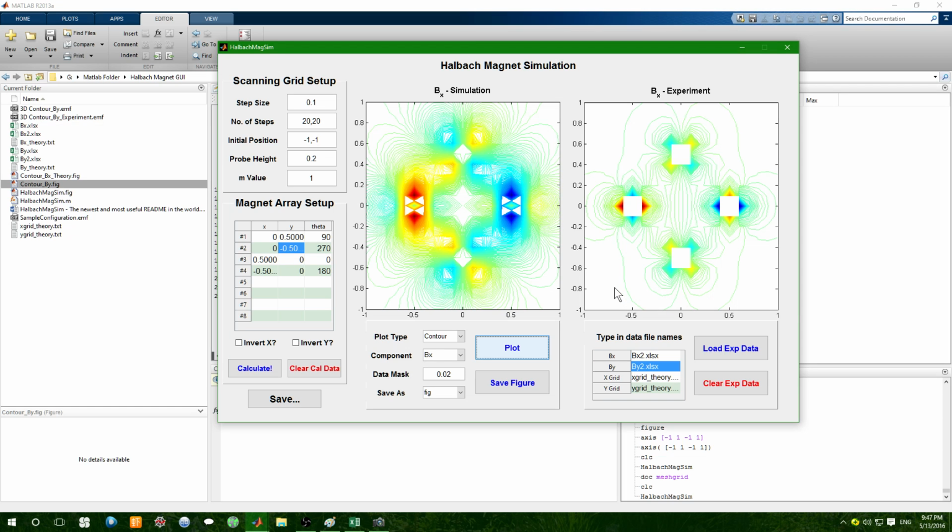This hidden minus sign may also be caused by an inappropriate orientation of the probe. Remember, the Hall probe is a vector probe, so it does have a sense of positive direction for measurement results. So if you flip the axial probe horizontally, or flip the transversal probe by 180 degrees, then you may accidentally introduce a negative sign in your data without knowing it.